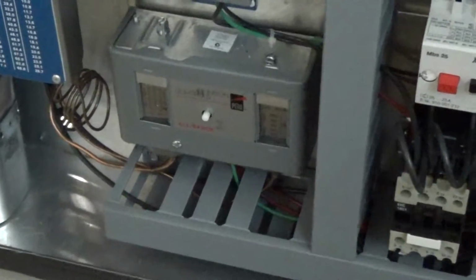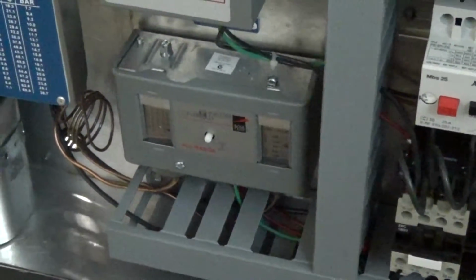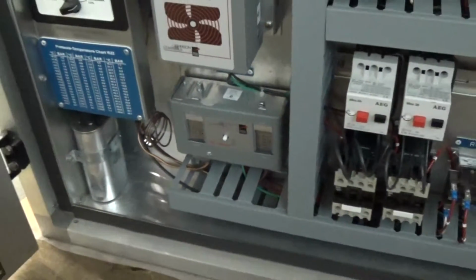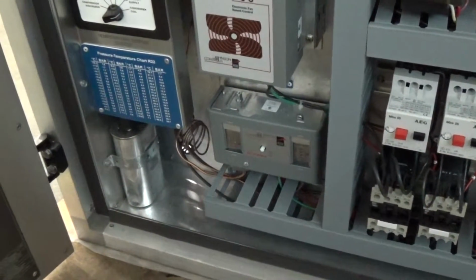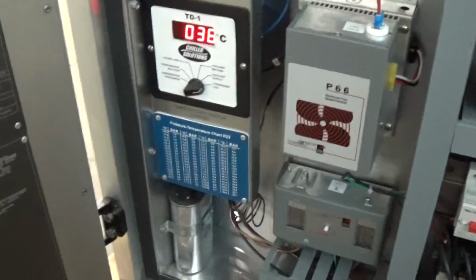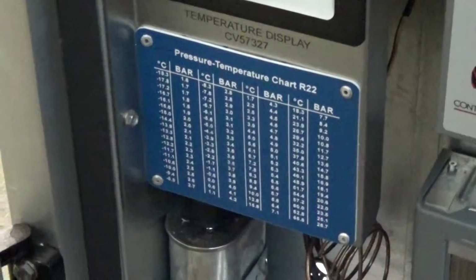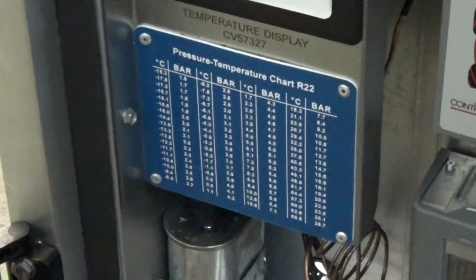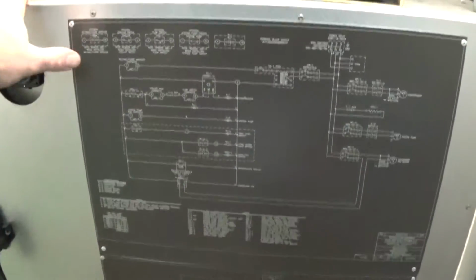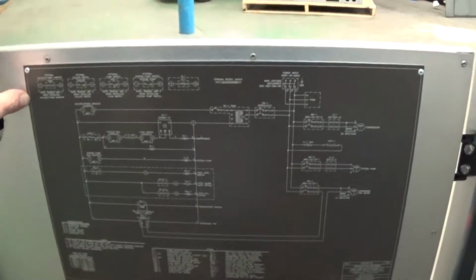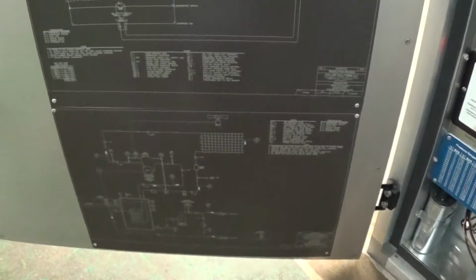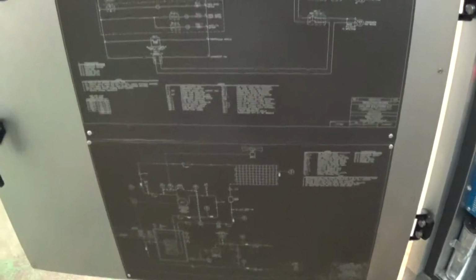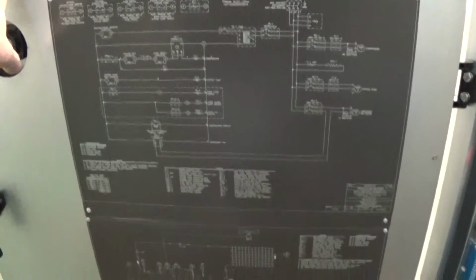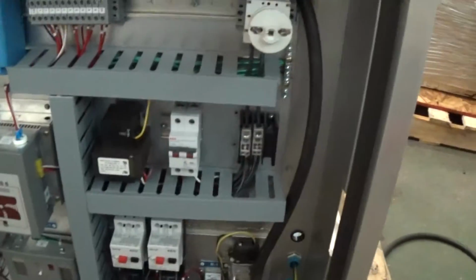This here is our high and low safety pressure switches, and they're pre-adjusted from us here to run at glycol temperatures. They do a nice thing. They put a pressure temperature chart here. That's outstanding, again, if you're on the phone with us troubleshooting for any reason. And they really put a nice placard here, kind of almost like an engraved plaque for the wiring and piping schematic for this unit.